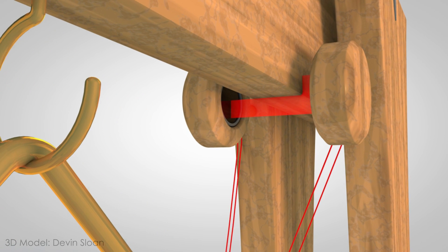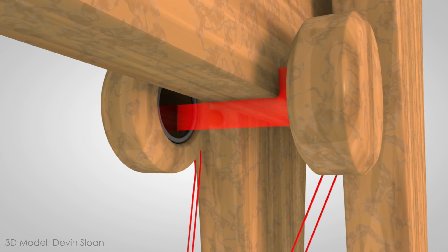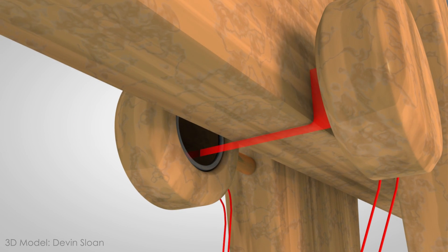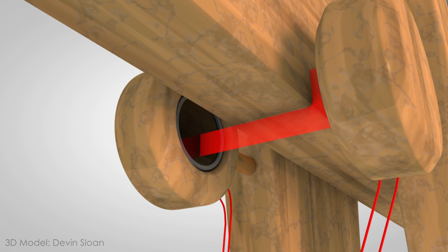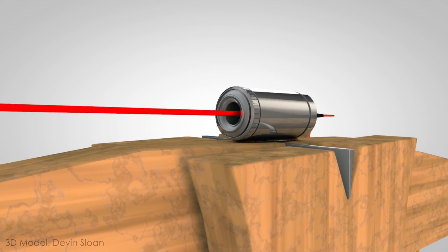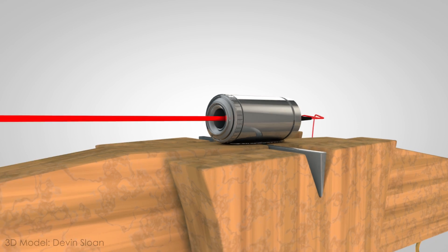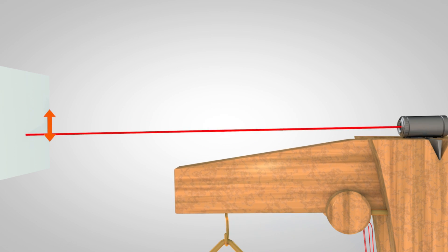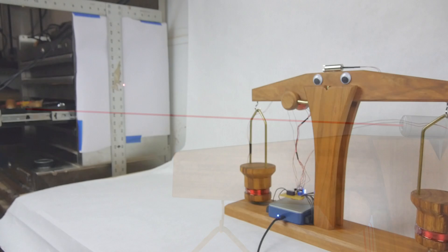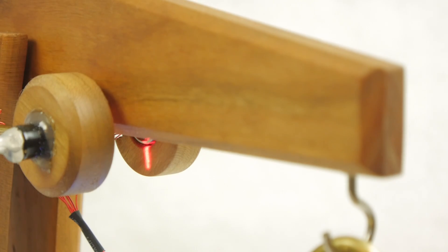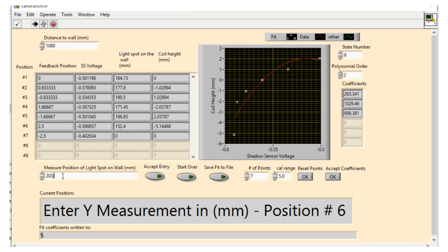To measure the position of the arm, the watt balance uses a shadow sensor, which consists of a photodiode and a laser line. As the balance moves, it gradually obstructs the path of the laser, changing the intensity of the light hitting the sensor. Another laser on top of the arm provides an optical lever for calibration. A small movement of the arm creates a large movement of the laser dot on an adjacent wall. By measuring the distance the optical lever moves for a few different arm positions, and comparing those to the corresponding readings from the shadow sensor, we can calibrate the watt balance so it knows the precise position of its arm.